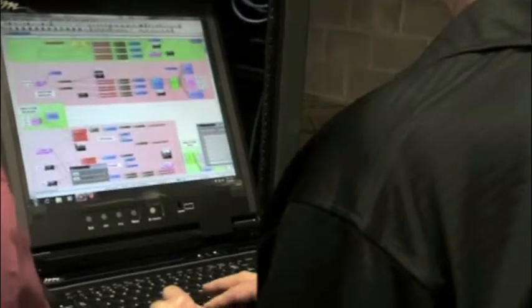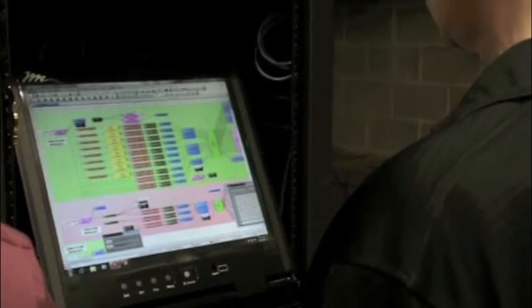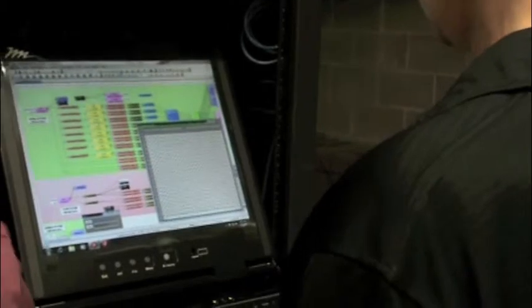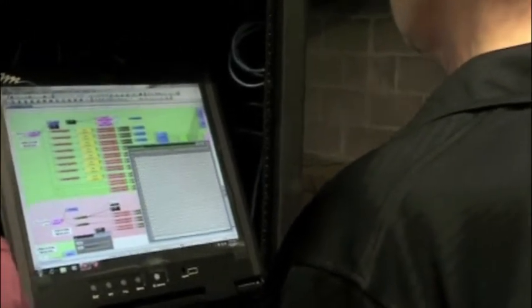If I look at the other systems, I've got a CobraNet coming in to input 8, which gets the fire page into there. Here's the gym DSP. I've got a fire page coming into there. And there's the main arena system. I've got a fire page coming in here, so that's on input 22. So that's how it works.